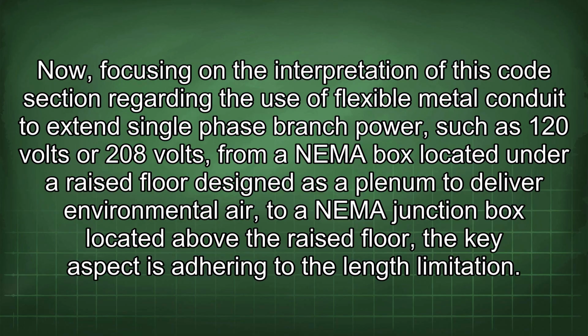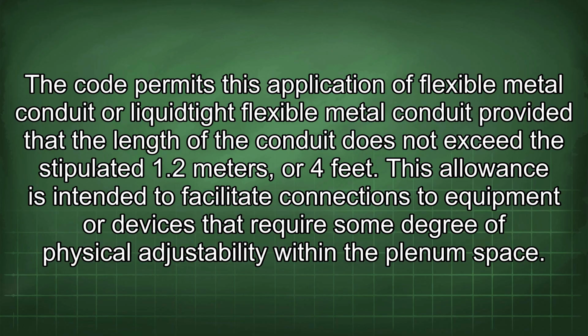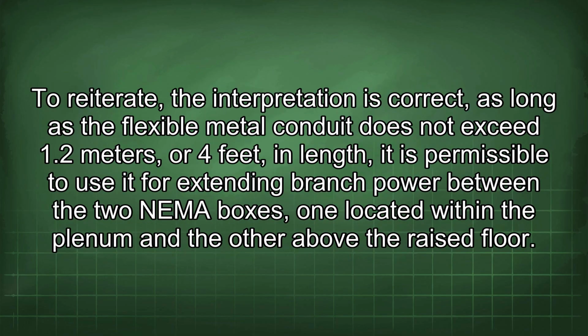The key aspect is adhering to the length limitation. The code permits this application of flexible metal conduit or liquidtight flexible metal conduit provided that the length of the conduit does not exceed the stipulated 1.2 meters or 4 feet. This allowance is intended to facilitate connections to equipment or devices that require some degree of physical adjustability within the plenum space. To reiterate, the interpretation is correct.